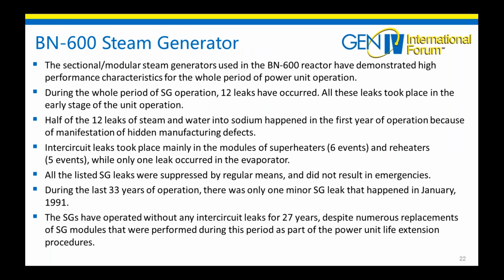The sectional modular steam generator used in the BN-600 reactor demonstrated high performance characteristics for the whole period of power unit operation. Overall, there were 12 leaks in the steam generator. All these leaks took place in the early stages of the unit operation. Half of these 12 leaks of steam and water into sodium happened in the first year of operation because of the manifestation of hidden manufacturing defects.